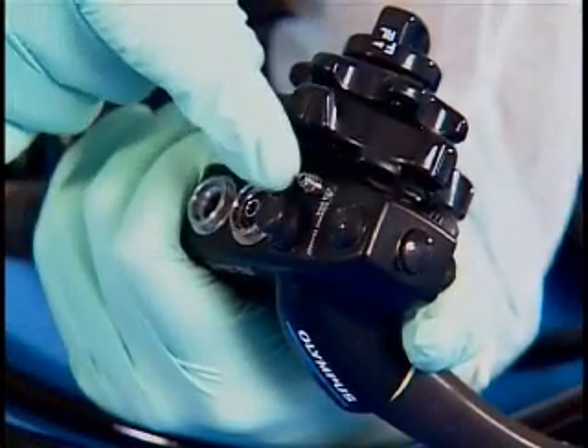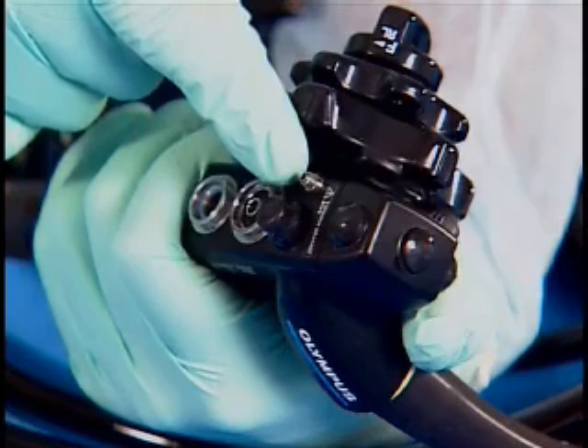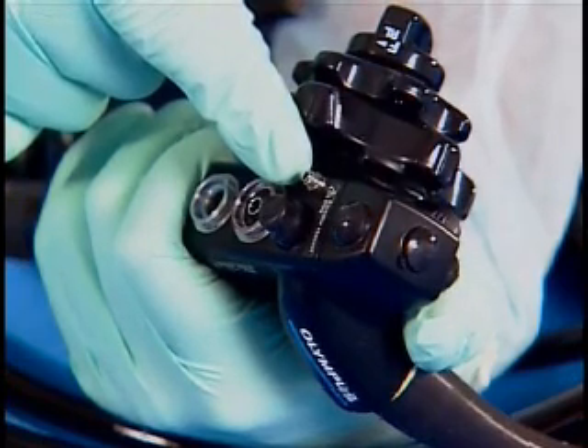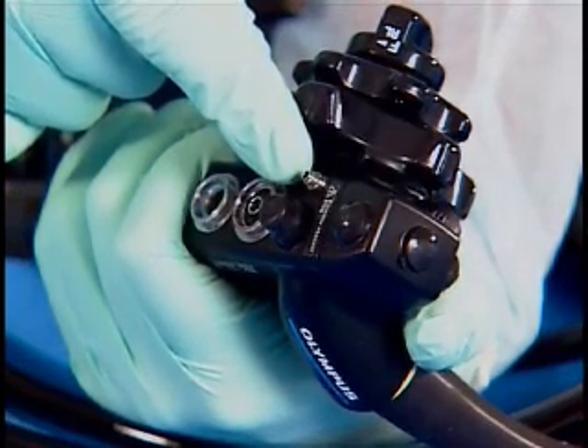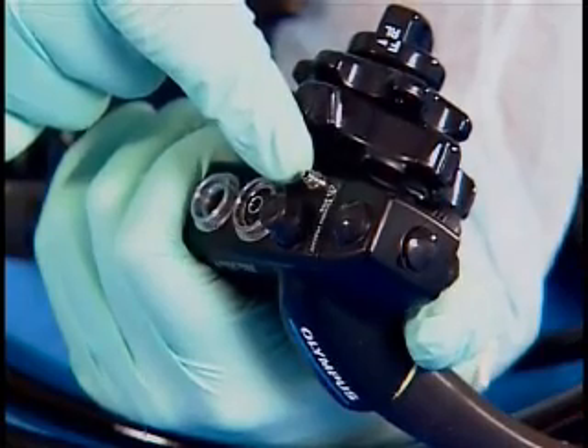Check the endoscope to determine if an elevator wire channel is present. If so, follow the additional steps outlined in this video to reprocess this channel as well. It should be noted that all of the internal channels of the endoscope must be reprocessed each time the endoscope is reprocessed, even if the endoscopist did not specifically use these channels during the patient's examination.